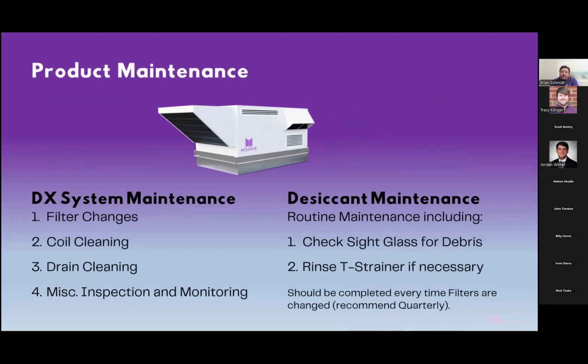So your normal DX system maintenance is obviously very applicable: filter changes, coil cleanings, drain cleanings, inspections, things like that. But on the liquid desiccant side, the only thing we really need to be concerned about is those T strainers. Just check those. Again, if they're contaminated, we can rinse them out.